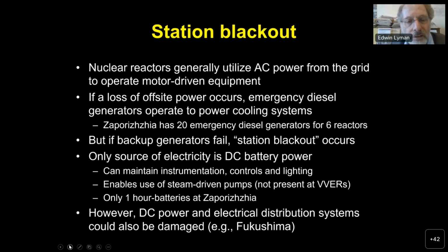And that's why those plants are designed that way, but that also creates a vulnerability, because if you have a loss of offsite power, which is not an uncommon occurrence, it can be caused by a wide range of natural disasters, then the plant has to go on backup diesel generator systems. And Zaporizhzhia is well equipped for that scenario.